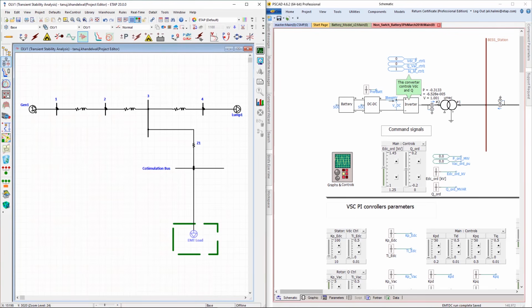This is a simple example showing a generator, a load, and an EMT load connected to our co-simulation bus. This EMT load is representing a battery, a DC to DC converter or a buck boost converter, an inverter, as well as a transformer connected to the BESS station. The boundary is essentially the BESS station that corresponds to the co-simulation bus. So therefore, the section of the system that you see in green is represented in PSCAD in full fidelity. This system will be solved in microsecond step, while ETAP is solving the entire network in 0.1 millisecond step.